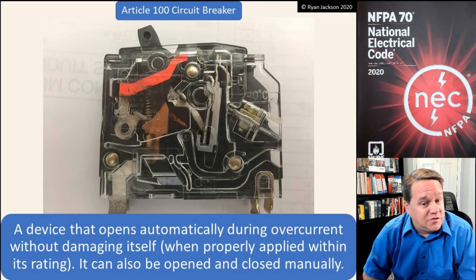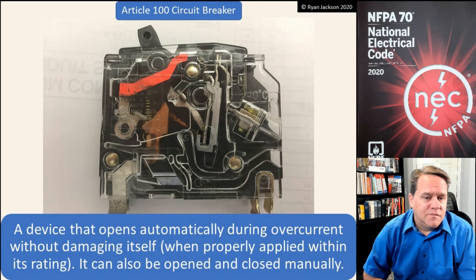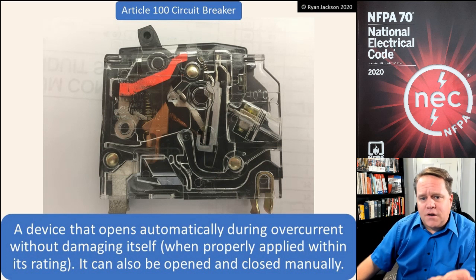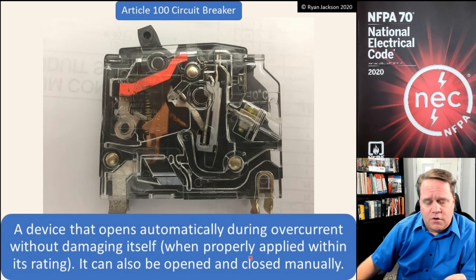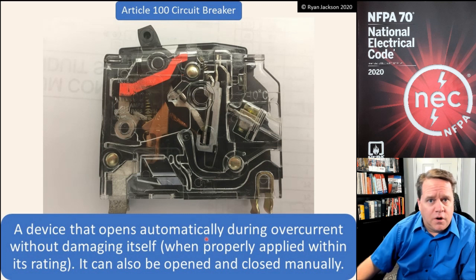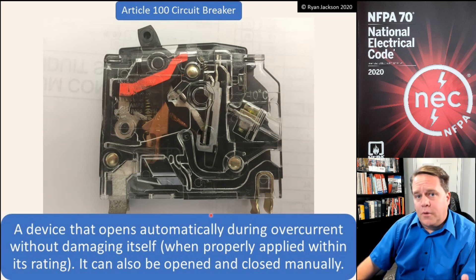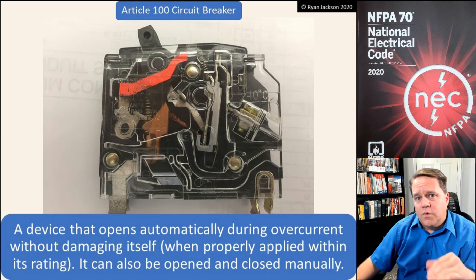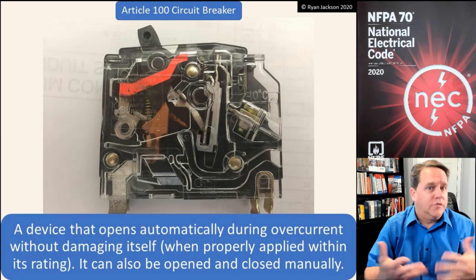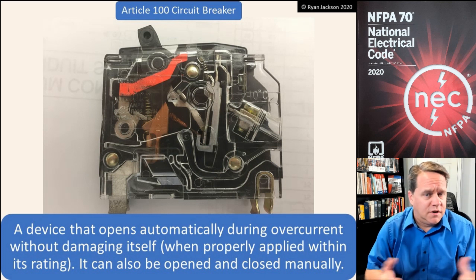A circuit breaker can also be opened and closed manually, unlike a fuse. A typical thermal magnetic circuit breaker has two components: the thermal part, which is for overloads, and the magnetic part, which is for ground faults and short circuits — or we could just call them faults or shorts.